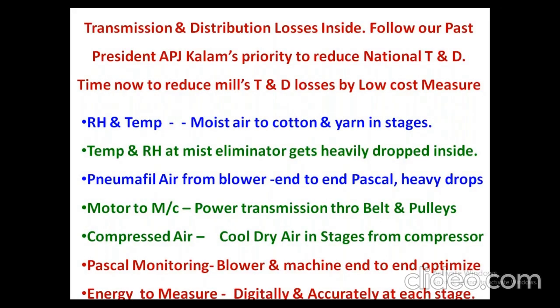As I was telling before, the textile mill is air operated, whereas moisture has to be ingressed at the cotton side, at the blow room side, at the carding side, at the spinning side, and on the autoconer side. The moisture ingress has to happen in the cotton and yarn in stages. If too much moisture is given to the cotton or in the spinning area, this is also a problem. So we have to go by stage. If you see the air conditioning plant or the humidification plant for a given mill, our Mr. Prakash is an air engineering expert. He is going to take the next session. It will be an excellent session on the humidification side.